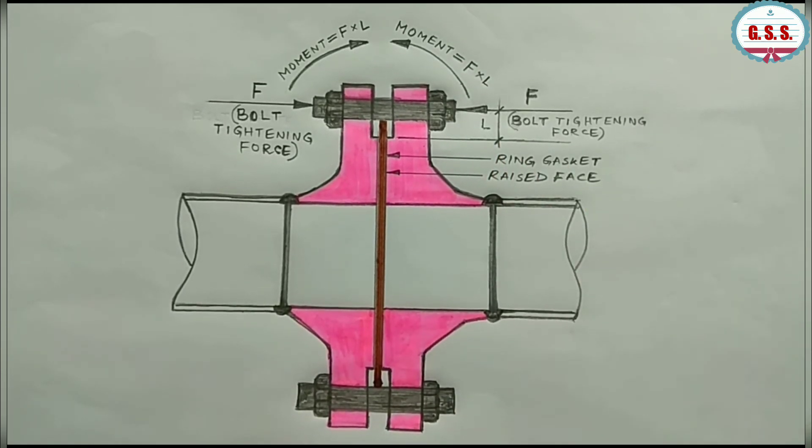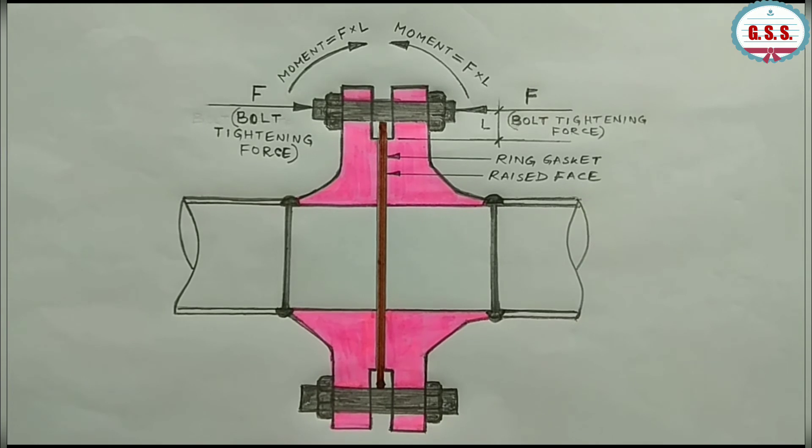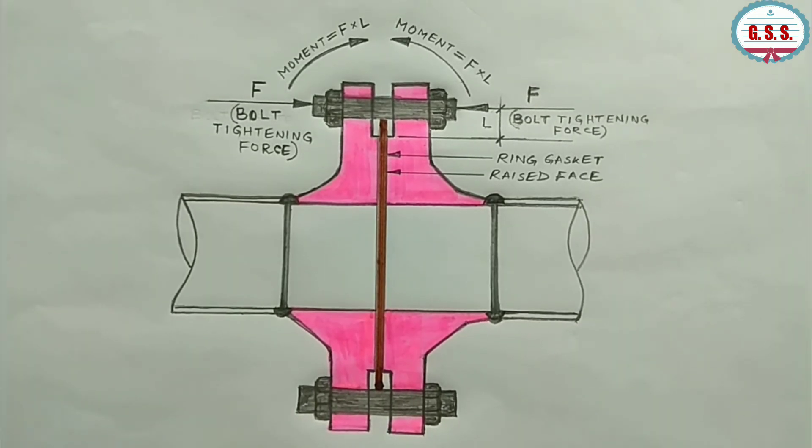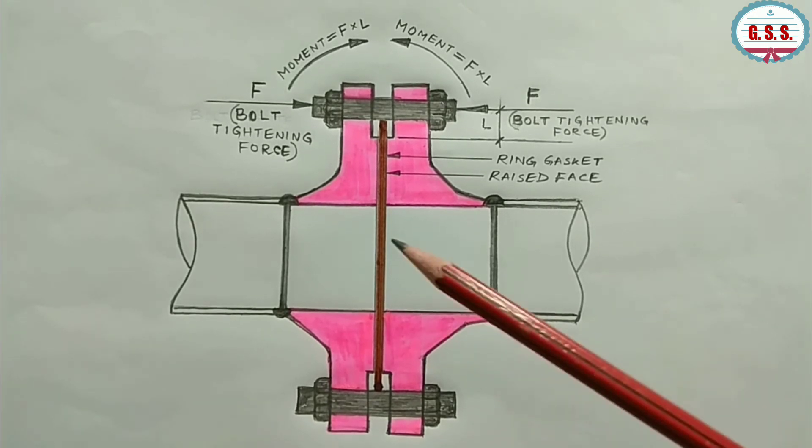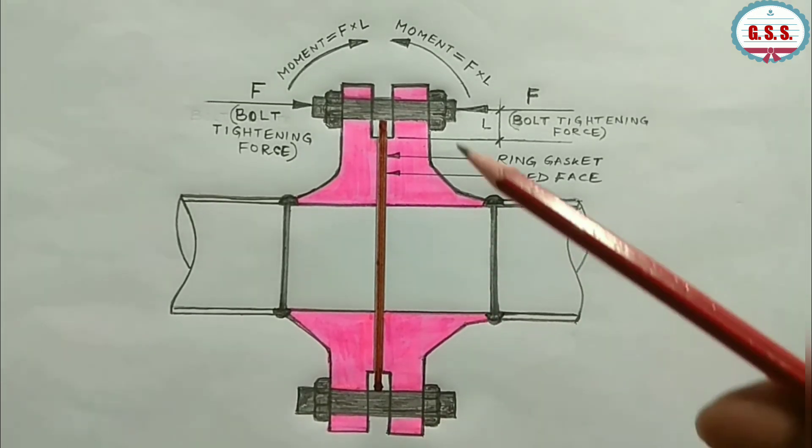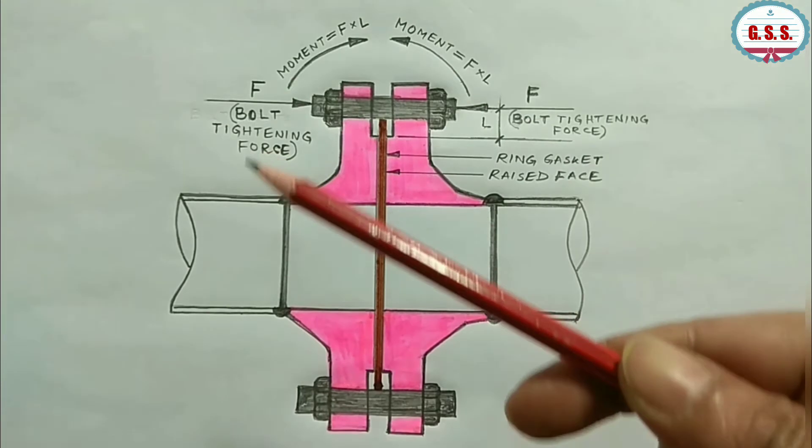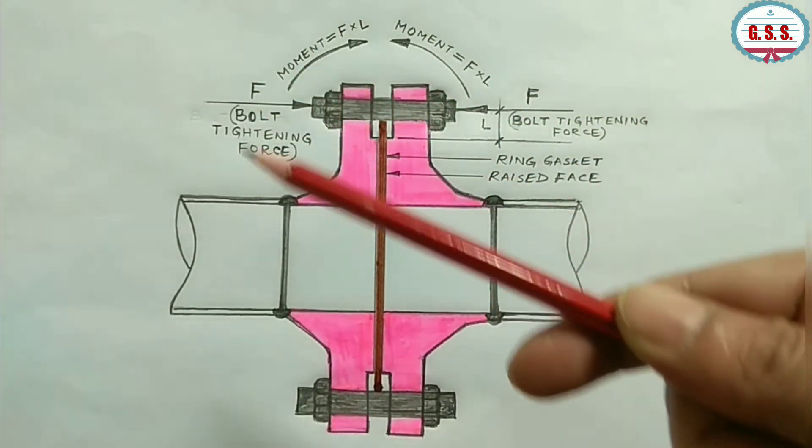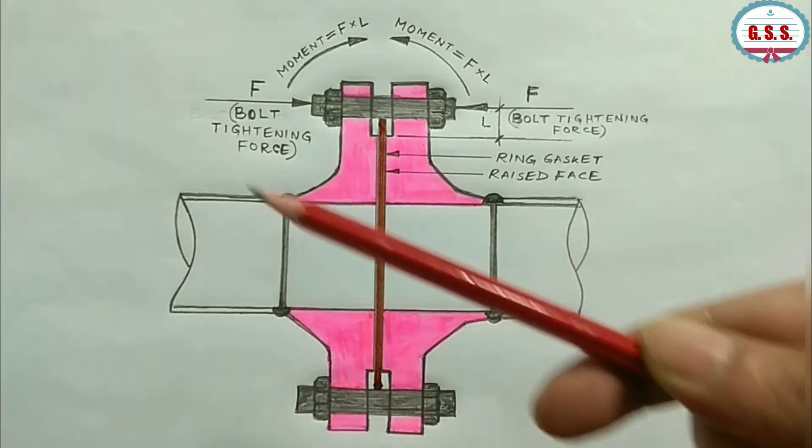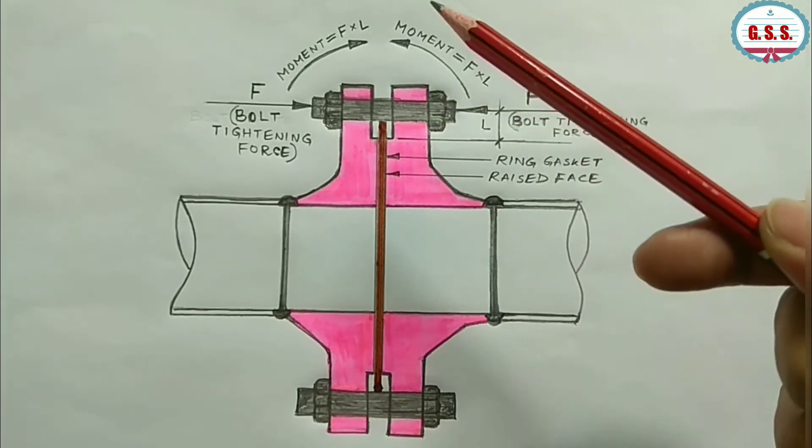Due to this moment, the gasket is more compressed. Also, in case of raised face flange joint, replacement of ring gasket is easier. We need not remove all bolts. We can remove only 50% of bolts from the upper portion of the flange joint and then take out the old gasket.